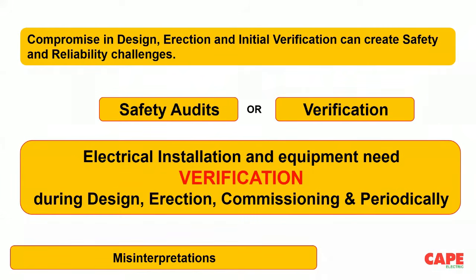So electrical equipment and the installation need verification during its design, erection, commissioning, and periodically. It's very much important. Not only during product testing, verification is required during design of the electrical installation, erection of the installation, commissioning of the installation, and periodically you should do verification.